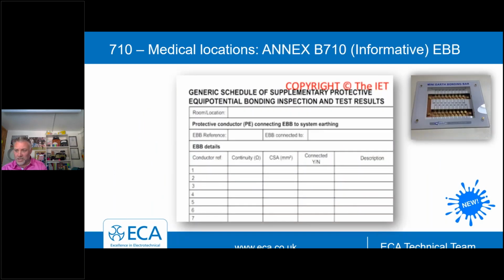So I think many of you have seen the use of earth bonding bars. IHEEM came to the national committees and they wanted an earth bonding certificate. So that's been designed by the committees and other people, and that's gone into the draft now. That's a way of recording the impedance of simultaneous accessible parts, typically in operating theatres and things like that. So that's now in a new annex.